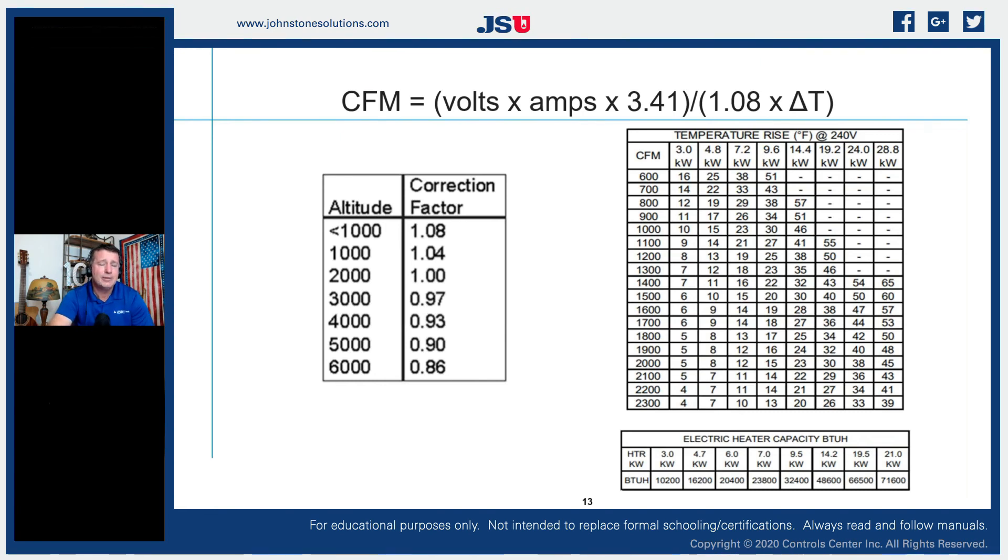We'll dive into the formulas a bit more later for those who like to calculate exact temperature rises. For an electric furnace it's straightforward: Volts × Amps × 3.41 (the BTU conversion factor from watts to BTUs), then divided by delta T (temperature rise) and 1.08 — a correction factor based on air density. As we change elevation we have to modify the formula based on air density. The 1.08 factor applies for anything less than 1,000 feet above sea level; above 1,000 feet we start derating the calculation due to the change in air density.